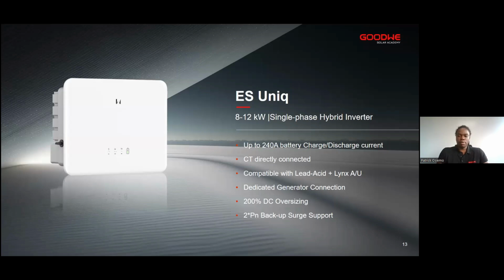ES Unique is compatible with the GoodWe latest indoor battery called the Lynx U and the Lynx A lithium-ion batteries, and can be used to retrofit installations that still have lead-acid batteries installed. So it's also compatible with lead-acid batteries. The ES Unique has a dedicated generator port to integrate AC generators to the hybrid.